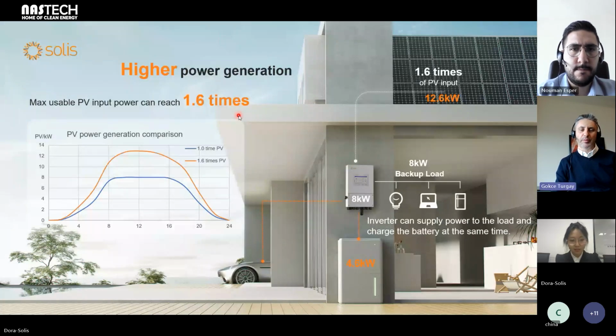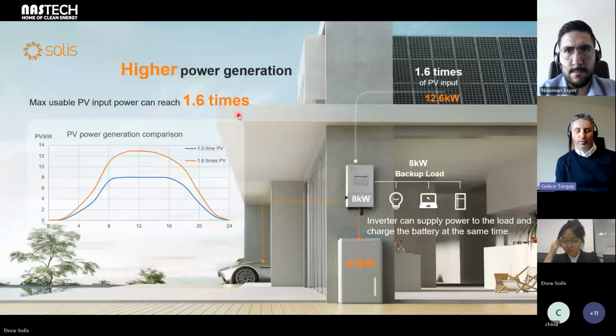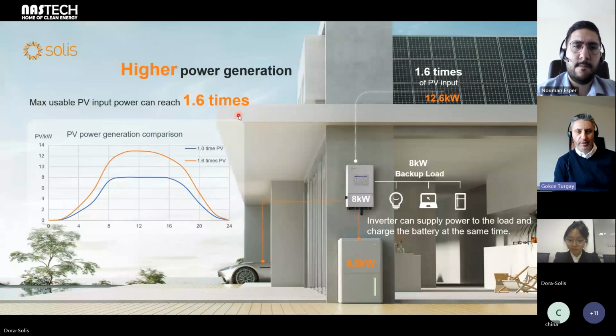So this is a typical case when you have an AC kind of load come in on top of everything working. At that time, maybe the power requirement, the load can go over the design capacity. This graphic shows us that up to 10 seconds, any given inverter in this range can work at 160% of its nominal capacity for up to 10 seconds.